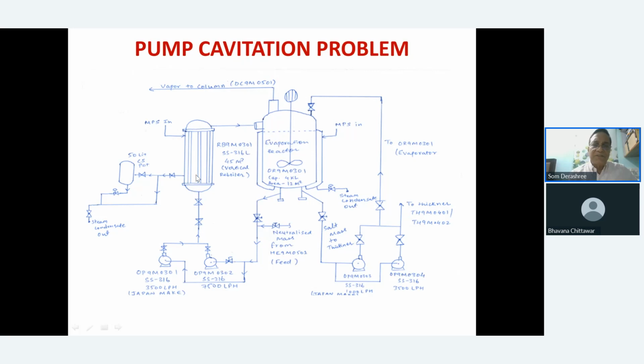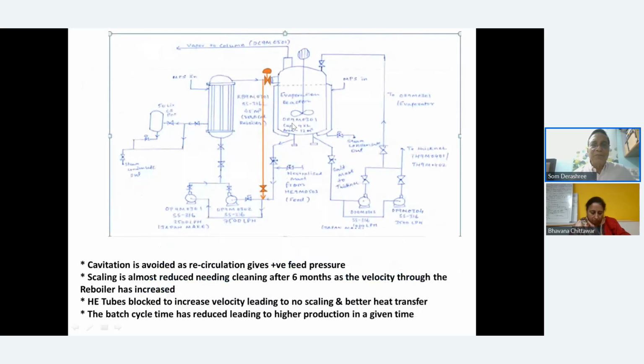But what was happening is after every 2-3 days they had to stop this unit because there was a lot of scaling happening here. And when they increased the pump speed, there was a lot of cavitation, because thick mass slurry was forming, getting solidified because of the evaporation of the solvents. So this was actually vibrating. They put a VFD, but with the VFD, when they reduced the flow, there was a lot of scaling. So every 2 days they had to stop the plant and clean all this. Then they put in a higher HP pump, and the problem did not get solved. The problem further aggravated. But they were living with this. What we did was a simple solution.